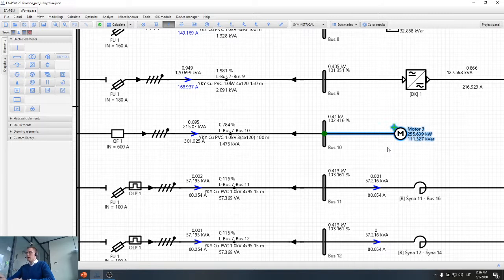However, nowadays when we have these data analytic things, it's actually possible to monitor the temperature of the motor. Motor temperature is also a very important parameter that can inform us about the motor operation state. So if it's possible, instead of negative sequence, it's possible to use temperature monitoring of the motor, and if the temperature exceeds the allowed level, it's possible to simply disconnect the motor from the network.